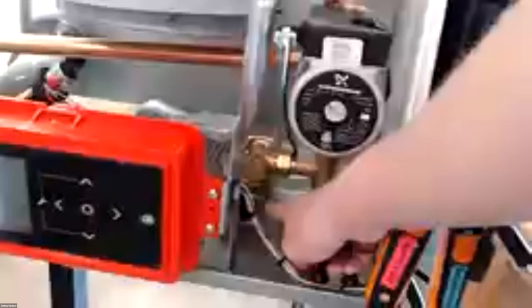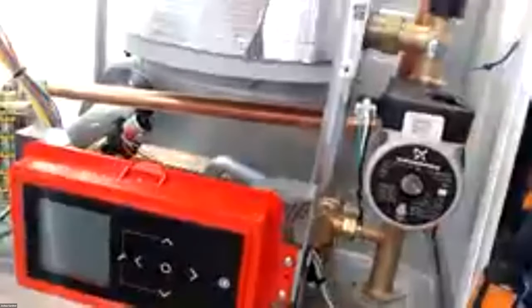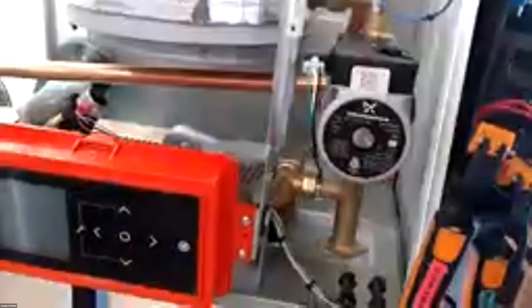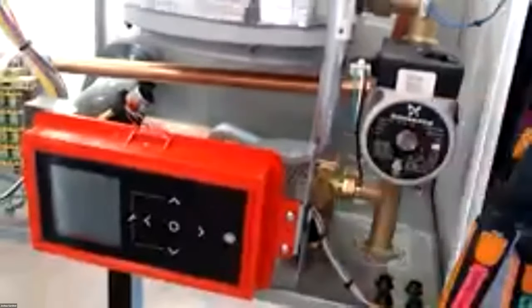You would also pull the flow sensor on the combis. Inspect those, see if there's any damage to the flow wheels. The pump, pretty much, as long as it's working, you should be fine. Low water cutoff to remove that, I'll show you guys.